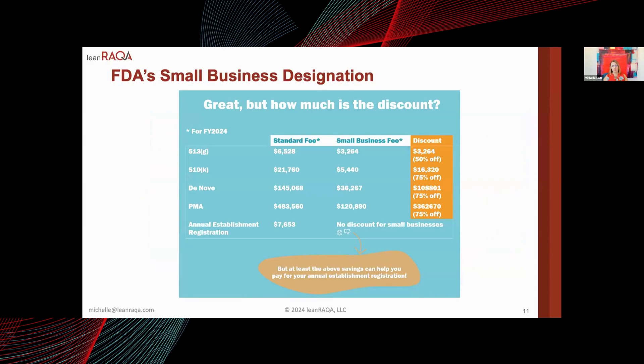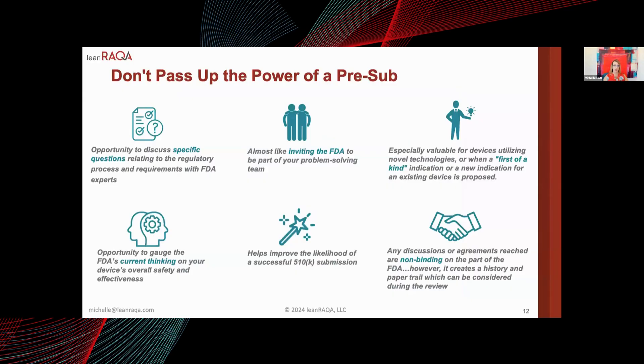The FDA also has a small business designation that can save you 50 to 75% depending on the type of submission. The pre-submission process is a powerful tool to ask FDA specific questions related to your regulatory process and technology. It gives you a snapshot of FDA's current thinking on your product — including guidance documents in draft or being discussed internally — information that is more than what's publicly available about your product.